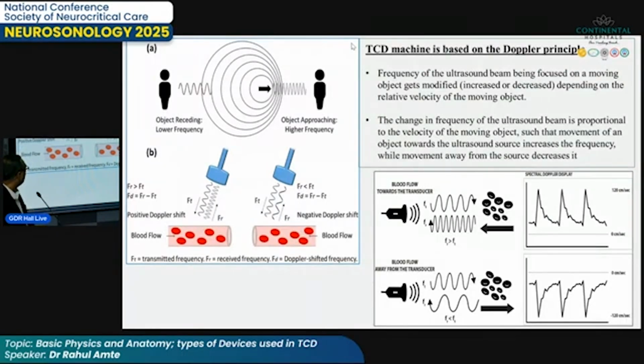It depends upon whether the blood is flowing away from the probe or towards the probe. Here you can see the probe emitting a specific frequency onto the red blood cells. If the red blood cells are moving towards the probe, the frequency reflected by the red blood cells will be more. So the received frequency will be more than the transmitted frequency, and on the waveform you will have a positive waveform above the baseline. But when the red blood cells or the flow are moving away from the probe, the reflected frequency we get is actually less, so the waveform will be negative, below the baseline. This is very important. The frequency of the ultrasound beam, when we focus on the object, depends upon the relative velocity of the moving object. The change in frequency is proportional to the velocity of the moving object. The frequency is more when it's moving towards us, and less when it's moving away from us.